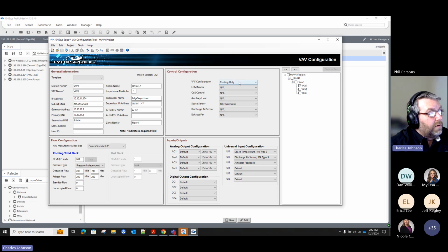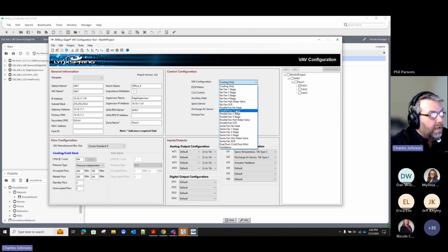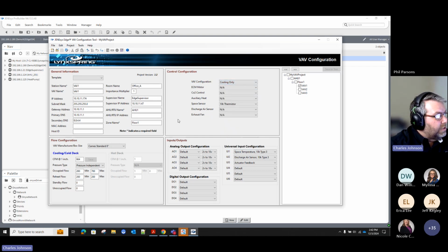But we have 22 different applications of the VAV that you can have, from a cooling only VAV to hot deck, cold deck, so dual duct. We can do up to 3 stages of heat, both with a parallel or a series fan in our pre-built application. In addition, we can choose space sensors, whether or not it's going to be an input, such as a 10K Type 3.